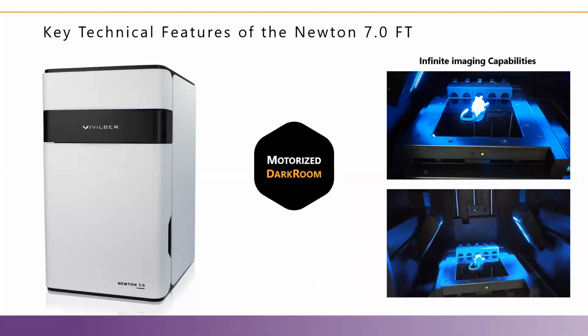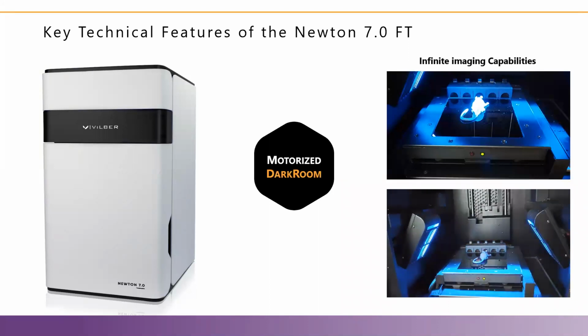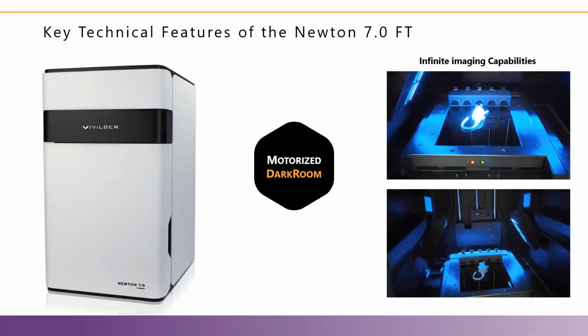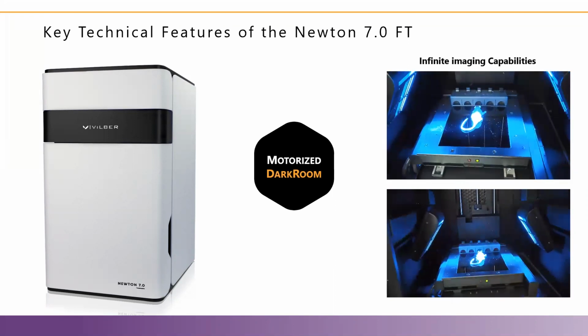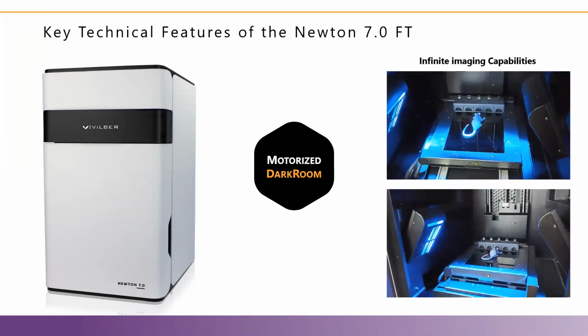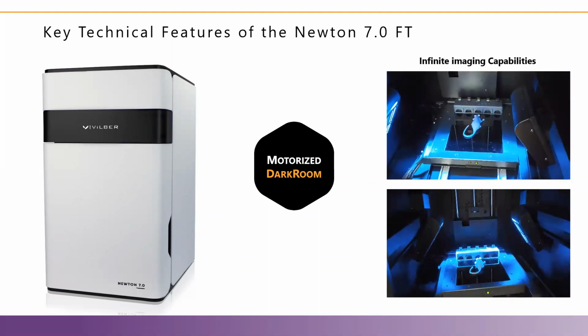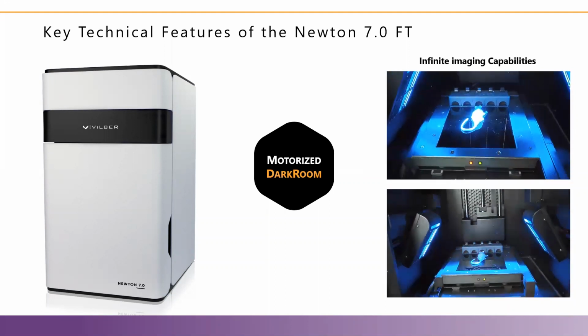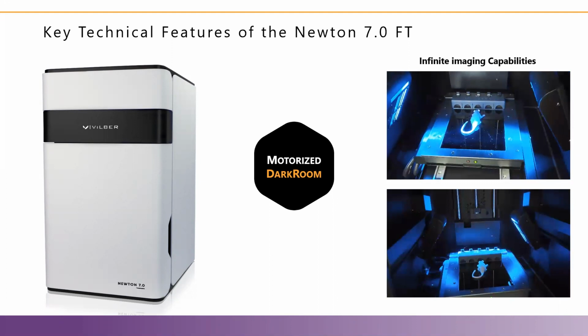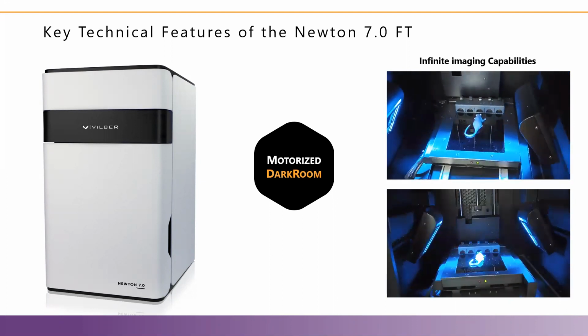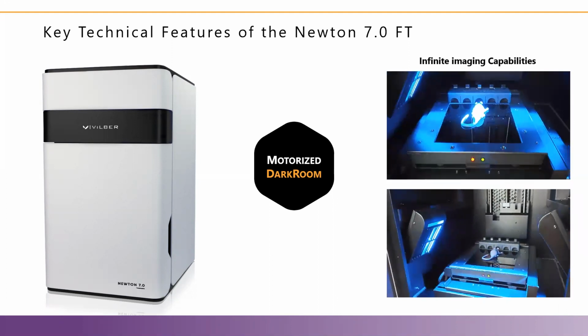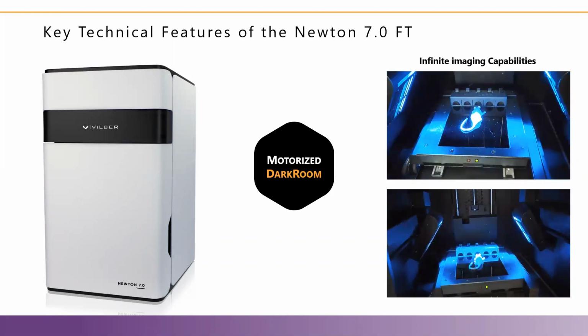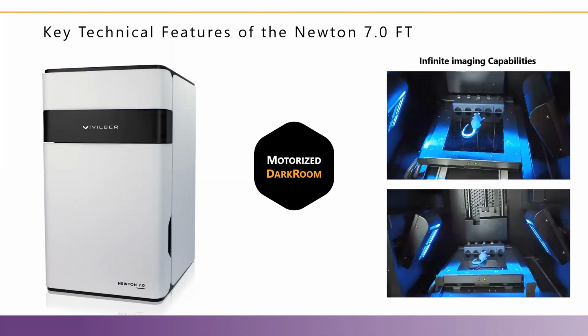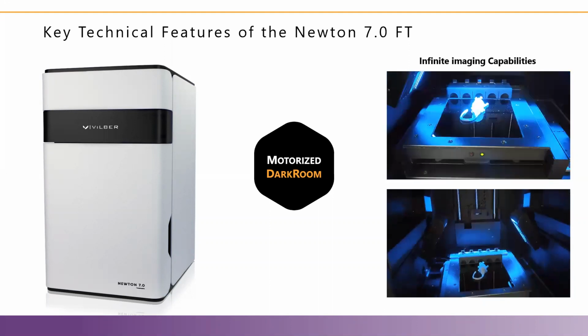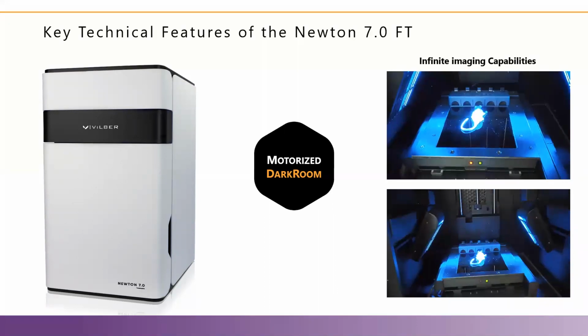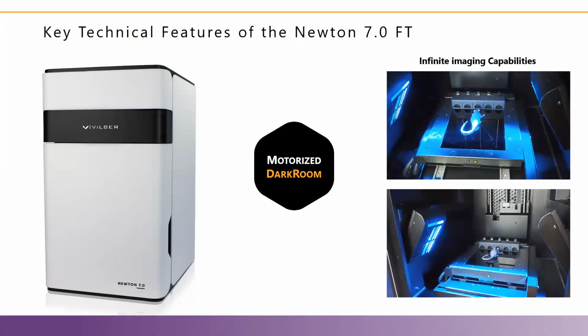The CCD camera is motorized on the Z-axis, and this is to accommodate various fields of view according to the number of animals that you want to image. So you can choose up to 5 mice or 3 rats to be imaged simultaneously. On the lowest position, the camera enters the macro imaging mode with a distance of only 6 centimeters to focus on a specific region of interest, such as the brain, and this will allow for gains in sensitivity. Since the closer the sample is to the camera, the better.